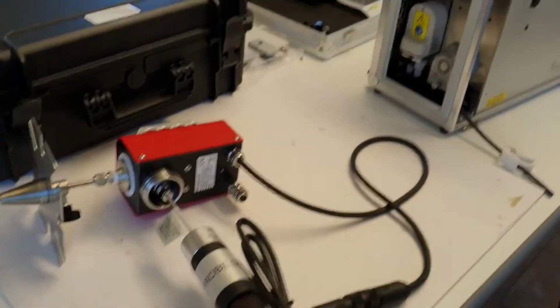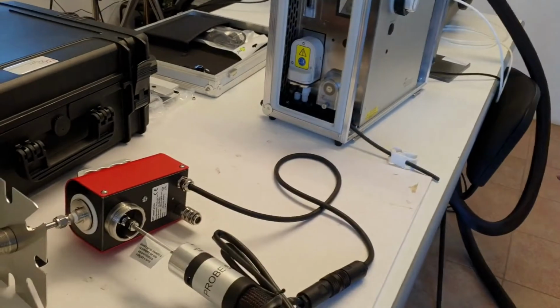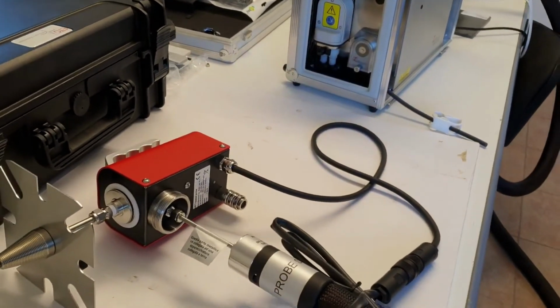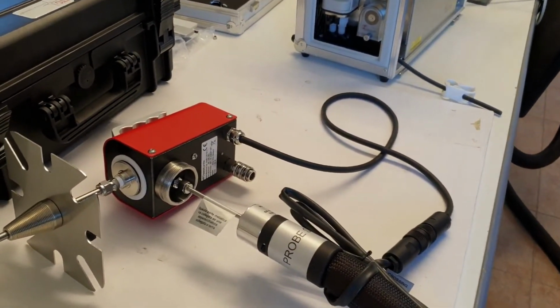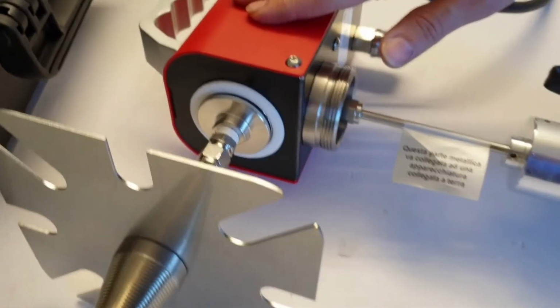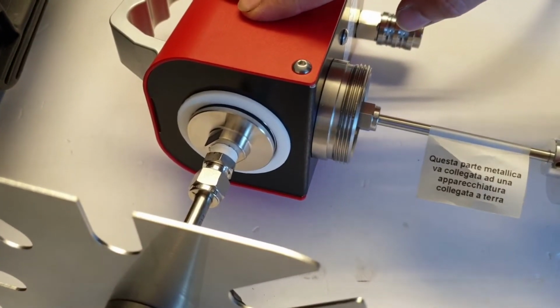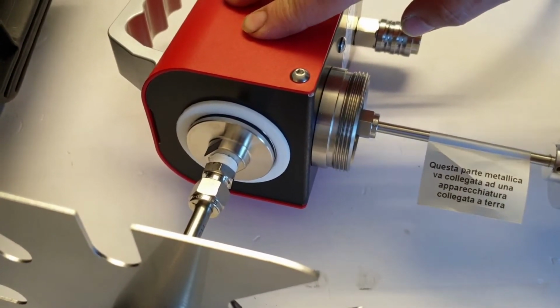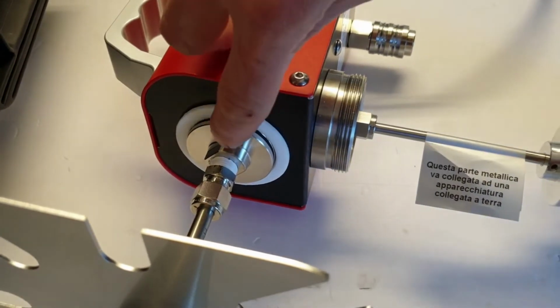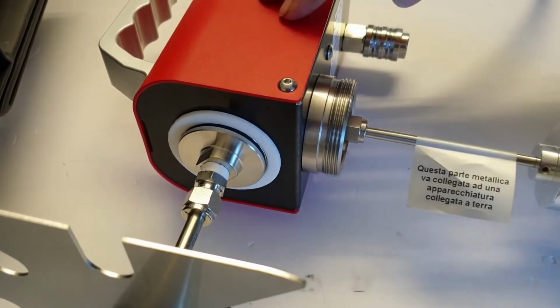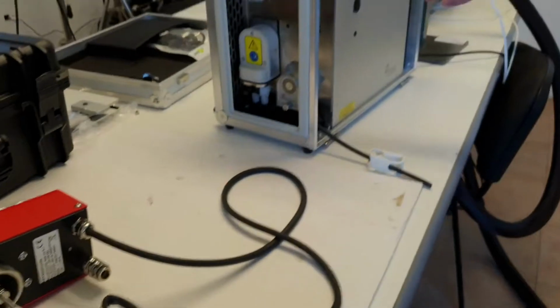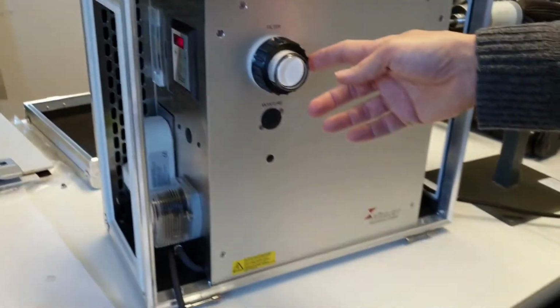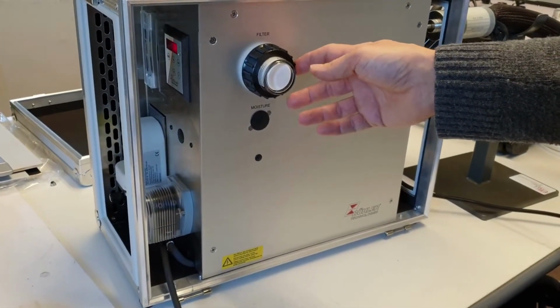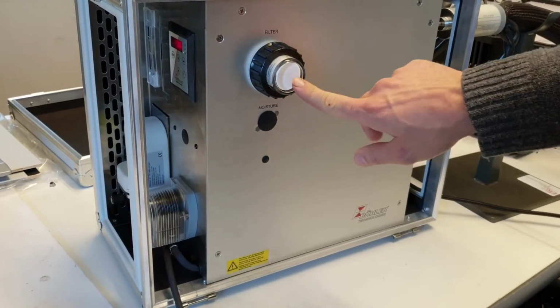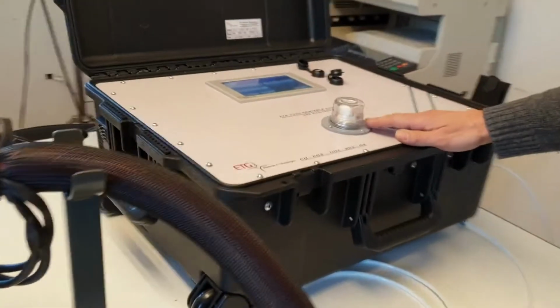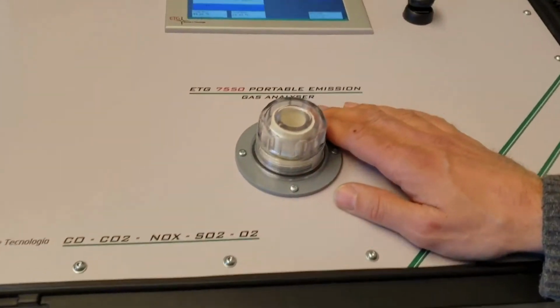On the complete system there are three different filters to remove the dust. The first one is inside the probe. To change this, it's necessary to unscrew here. The second one is on the sample conditioning unit panel, this one. And the last one, the third, is on the panel of the analyzer.